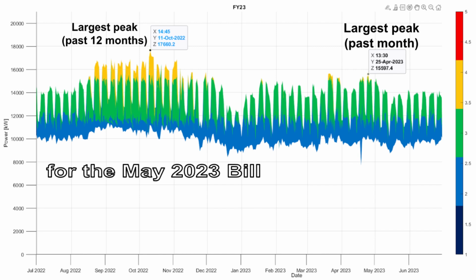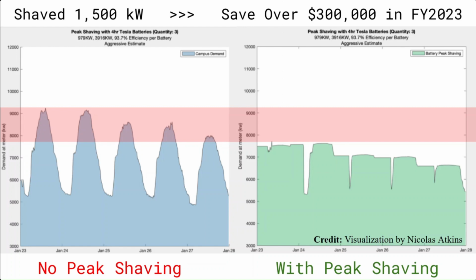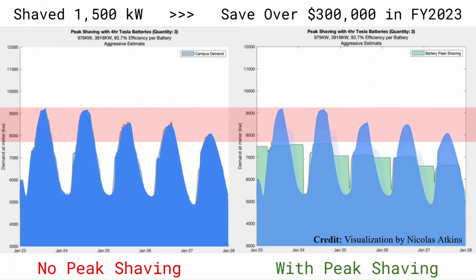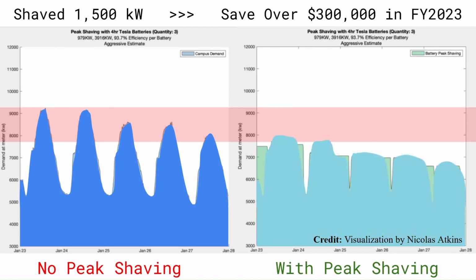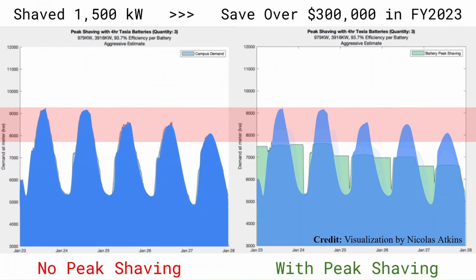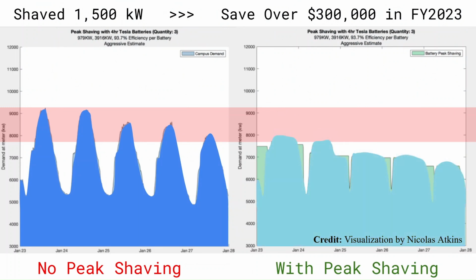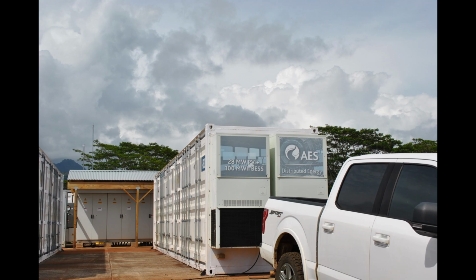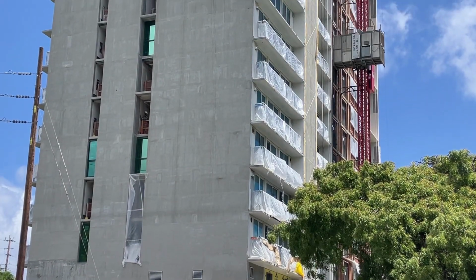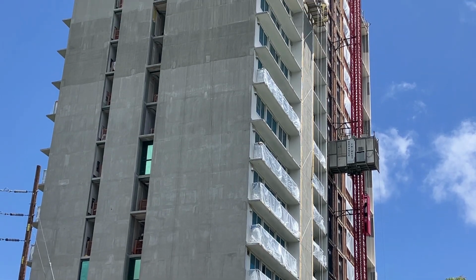Currently, we are working on ways to shave around 1,500 kilowatts from the peak demand days. This example shows what peak shaving 1,500 kilowatts would look like over 1 week. As you can see, when this is done, the area under the curves remains the same, meaning that this does not change the total amount of power we are buying from HECO. Rather, it limits how much power we buy at once, and flattens these peaks by using either batteries or changing our behavior on campus. In order to meet our renewable energy goals, we must first understand what is happening now and how we can move forward.